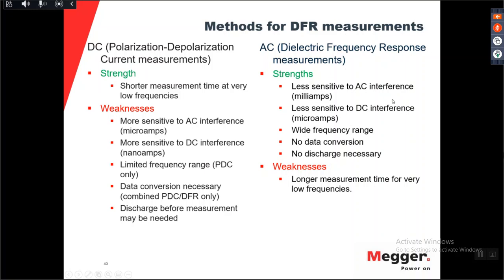And if you have an AC measurement, you don't need to worry about the DC interference at all, as it has no effect on the calculation of an AC current. And you don't need to do any data conversion, and the repeatability is much, much better. The weakness is that it takes slightly longer time.